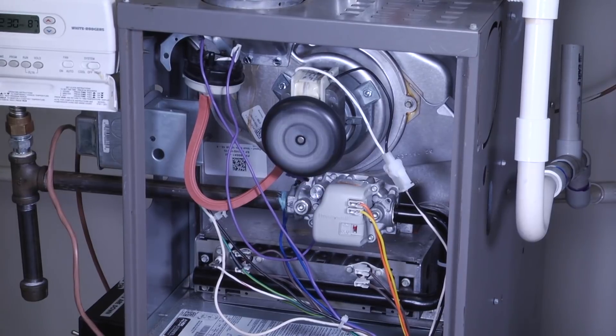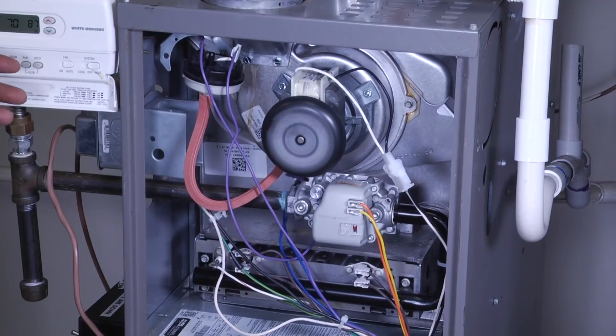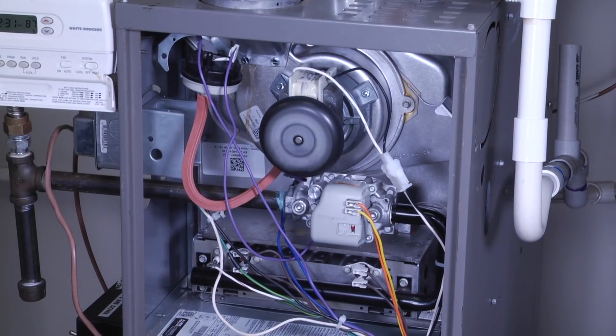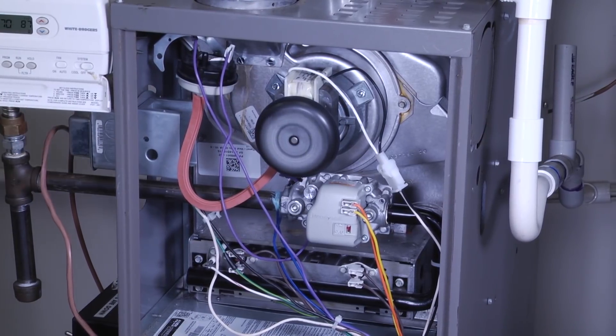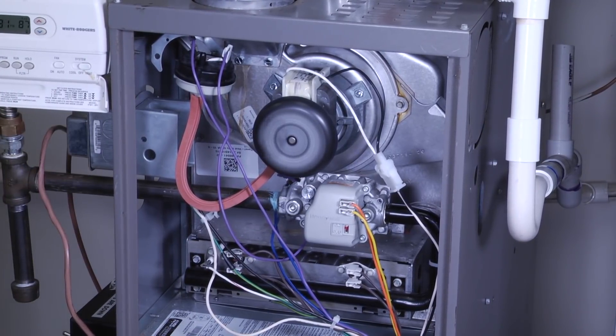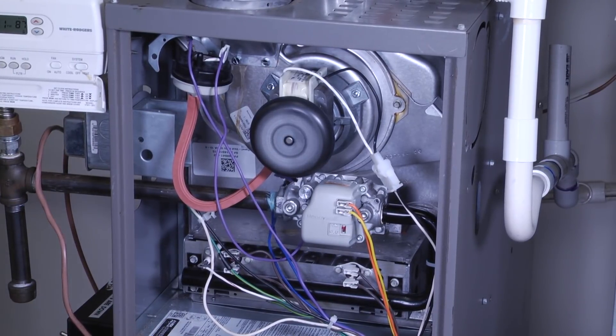And so that's the complete sequence of operation for a gas-fired furnace. First the call for heat, our inducer motor, the pressure switch, our hot surface igniter glows, our gas valve opens, our flame sensor proves flame, our blower motor engages, and then we reach our set temperature.